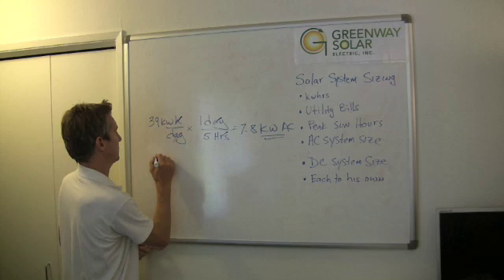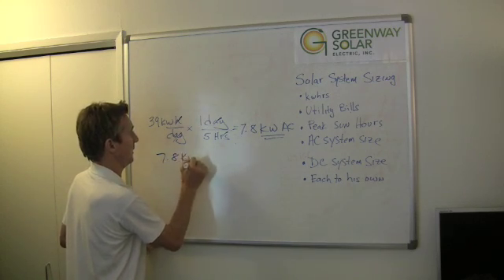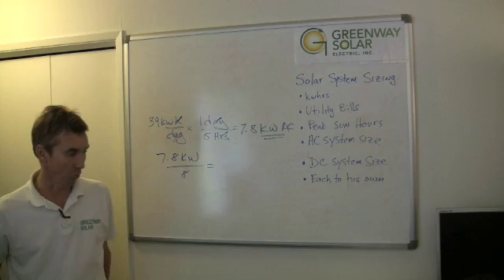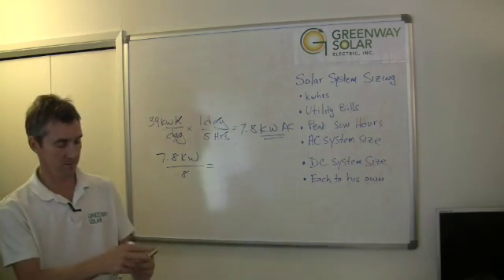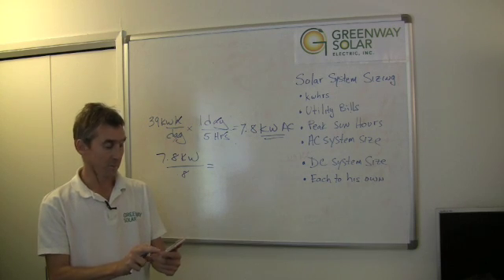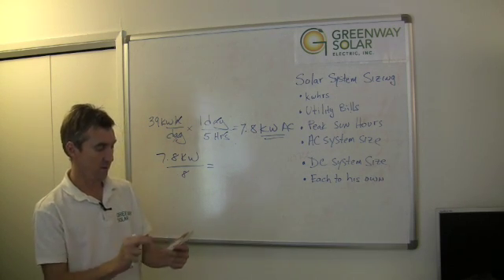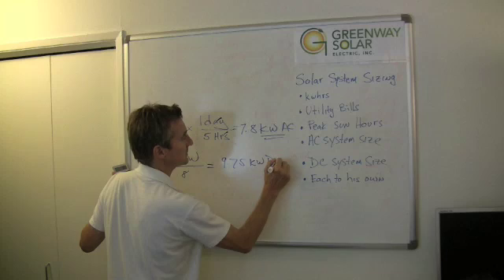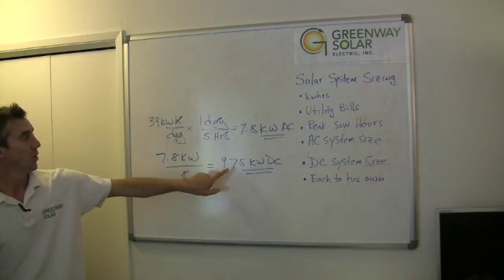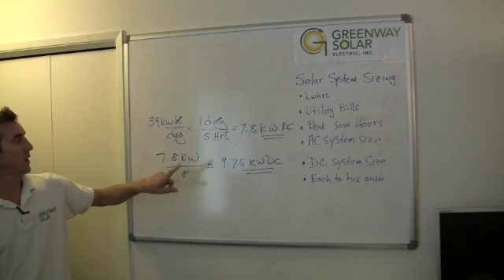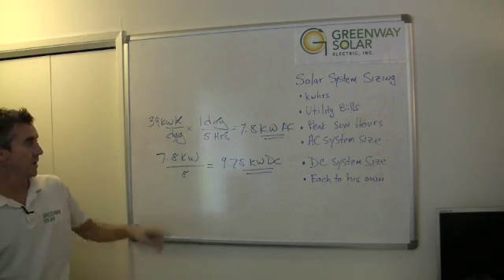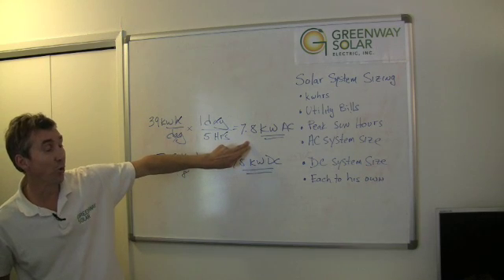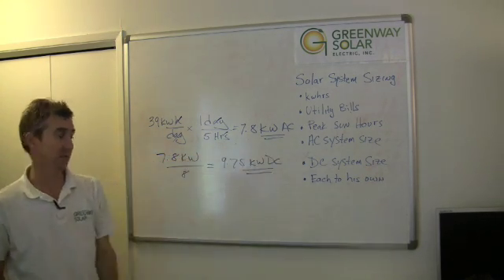So we're going to do this. We're going to do 7.8 kilowatt and we're just going to divide by 0.8. That's going to give us about 20% more. So if I do that, 7.8 divided by 0.8, so that gives us a 9.75 kilowatt DC system. So in order to produce 39 kilowatt hours a day, we would actually need a 9.75 kilowatt DC system, which is more or less equivalent to a 7.8 kilowatt AC system.